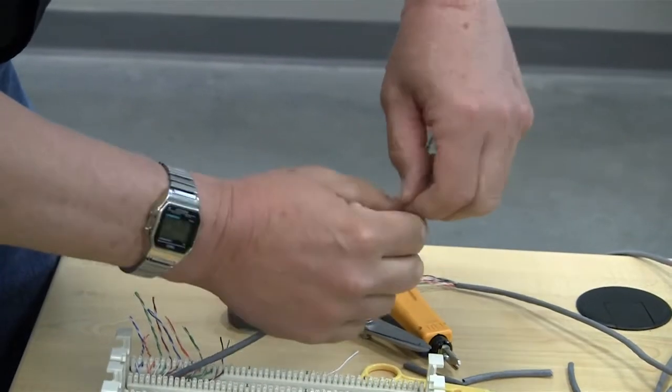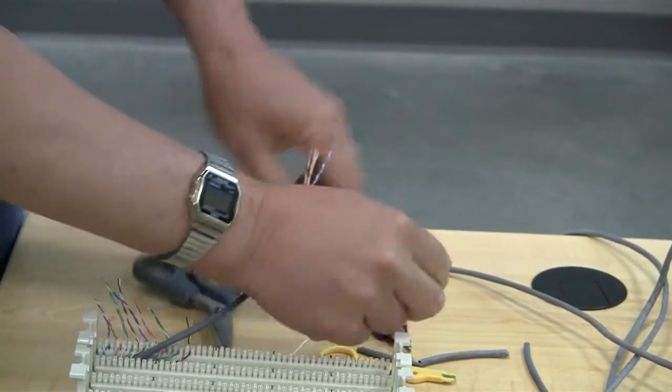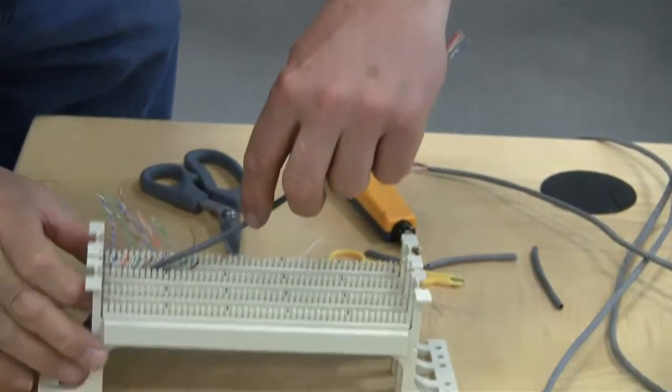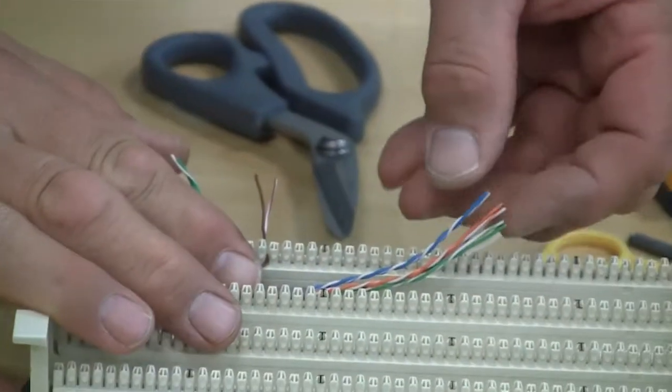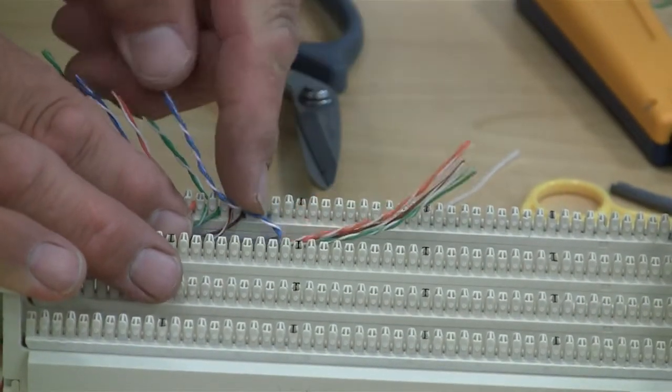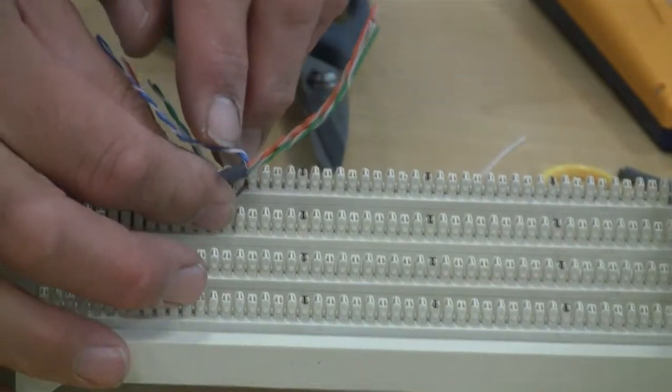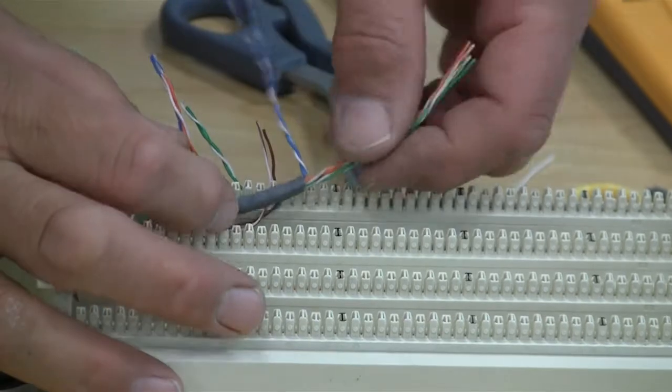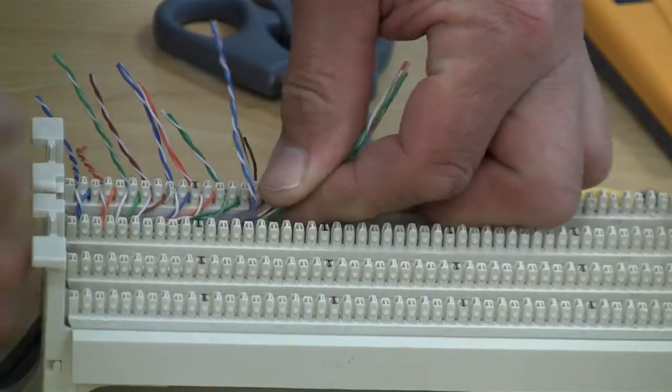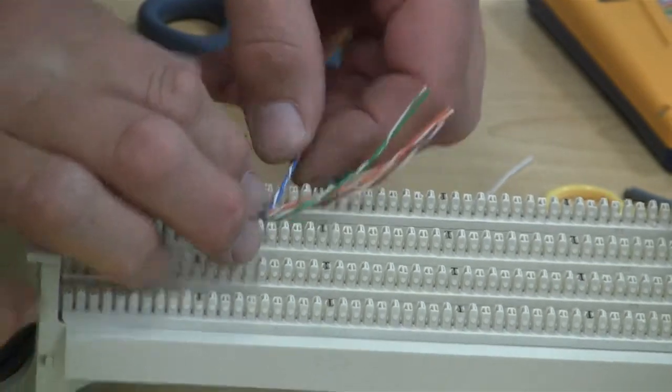Some of the things we're looking for that we don't want to do with the data cable is leave the jacket too long and bring the pair back against the jacket. This is basically a kink right here which will slow our data down, so we want to make sure that we do not have kinks. We want a nice sweep coming out of the jacket.